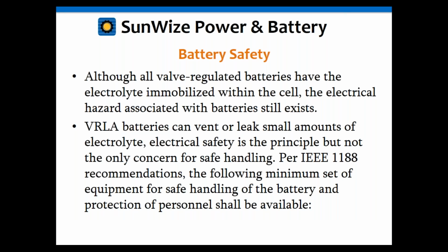Although valve-regulated batteries have immobilized or starved electrolyte, so it's not wet like a flooded battery, there's still a hazard. There's a possibility that acid can still be present. It can leak out of the valve that regulates pressure in the battery if it's been pressurized for some reason, like overcharging, and had gas buildup. There can occasionally be a little bit of acid associated with that. Not much, but the hazard is still there, so keep that in mind.